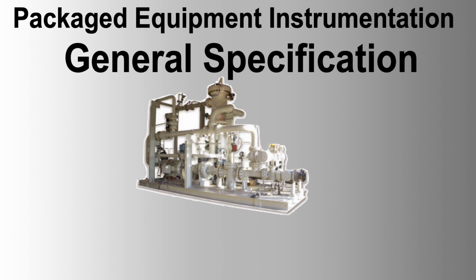Simulated functional test. Equipment must be energized for the duration of the test, including externally powered panel-mounted indicators. Dummy loads should be fitted where necessary. The test must ensure the correct operation of alarms, interlocks, and time delays. Simulated signals between the local control panel and the DCS should also be tested.